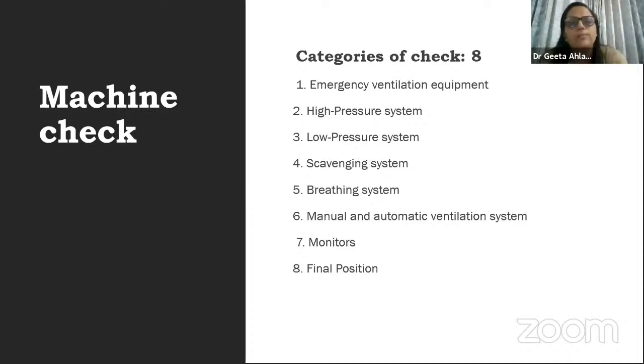So when you talk about the checklist, we should first talk about the emergency ventilation equipment. Even if this machine standing behind you fails, then what? The high pressure system falters, then what? Each system should individually be checked: high pressure, low pressure, scavenging system, your breathing systems, all the ventilation that we've talked about, all the monitors that you have. And what is my final position after checking all this? Should I go ahead or not? Am I equipped or am I not equipped?